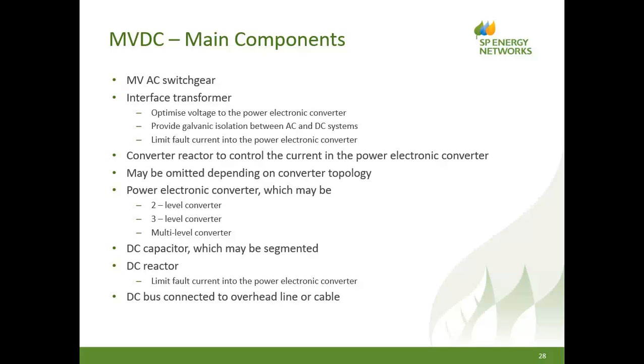The power electronic converter itself can have a variety of different topologies. Historically, two-level converters or three-level converters have been used, or multi-level converters are now becoming more common. And for the topology that General Electric are proposing for this project, they're looking at a multi-level arrangement to help produce a much better sine wave. The DC capacitor, which I've shown in my single line diagram, may not be a single DC capacitor. More likely, it will be segmented into small DC capacitors, each controlled by the multi-level converter.